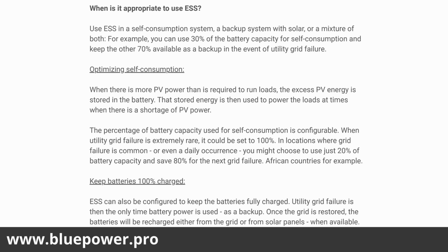So optimizing self-consumption: when there is more PV power than is required to run loads, the excess PV energy is stored in the battery. That stored energy is then used to power the loads at times when there is a shortage of PV. The percentage of battery capacity used for self-consumption is configurable. That's settable under the ESS system.